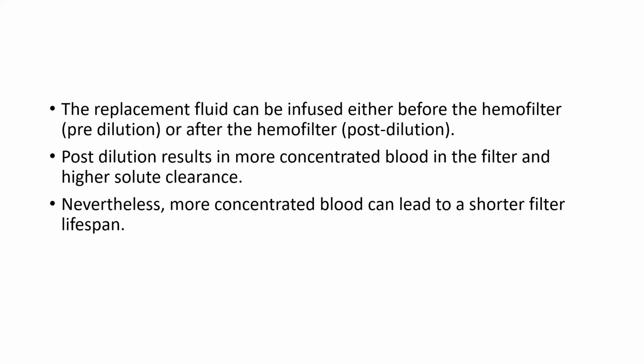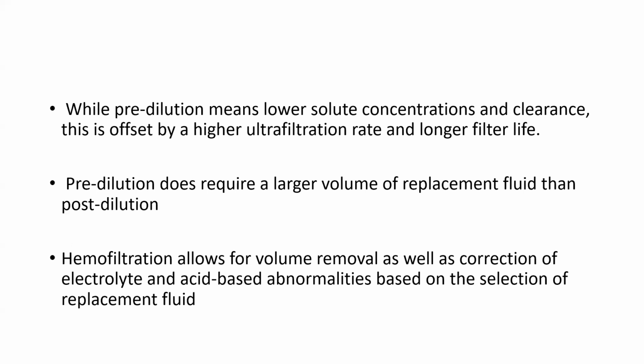The replacement fluid can be infused either before the hemofilter or after the hemofilter. So post-dilution results in more concentrated blood in the filter and higher solute clearance. Nevertheless, more concentrated blood can lead to shorter filter lifespan. While pre-dilution means lower solute concentration and clearance, this is offset by a high ultrafiltration rate and longer filter life.